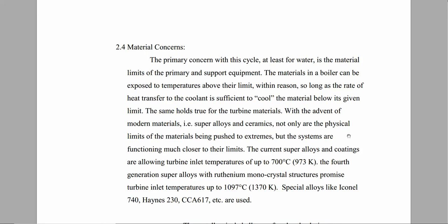With the advent of modern materials, that is super alloys and ceramics, not only are the physical limits of the materials being pushed to extremes, but the systems are functioning much closer to their limit. The current super alloys and coatings allow turbine inlet temperatures of up to 700 degrees Celsius.